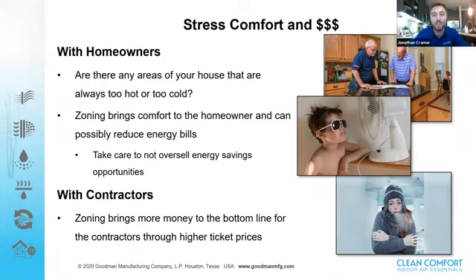Now, obviously, you want to be a little bit careful when you say that zoning can save them energy, just because there is obviously a chance where this homeowner lives in Houston, Texas, and they want to be at 68 degrees in all 3 zones. Well, for that case, you're running your system just as often, if not more, than you were when you just did not have zoning. So you just want to be a little careful and explain to them the areas and ways it can actually save them.